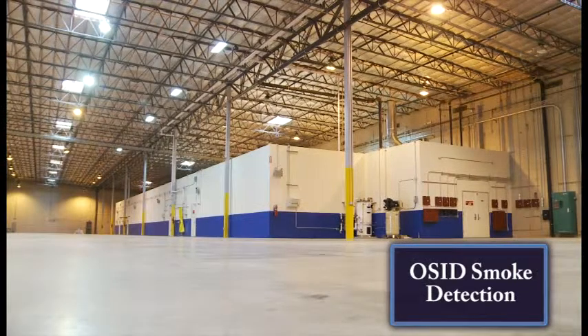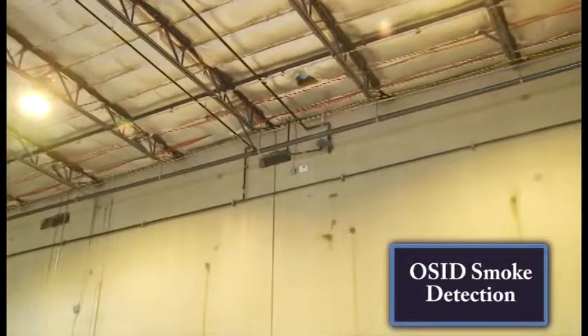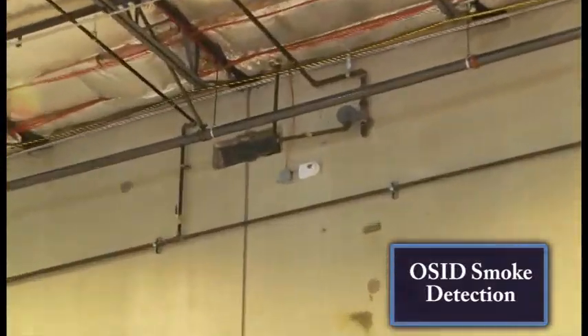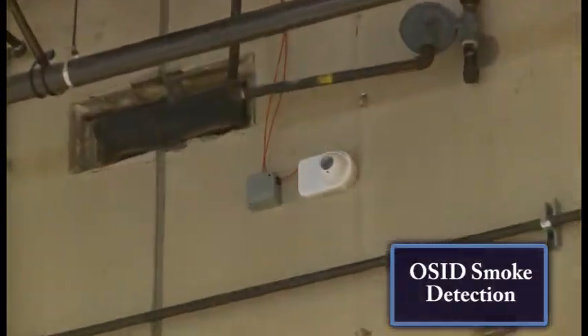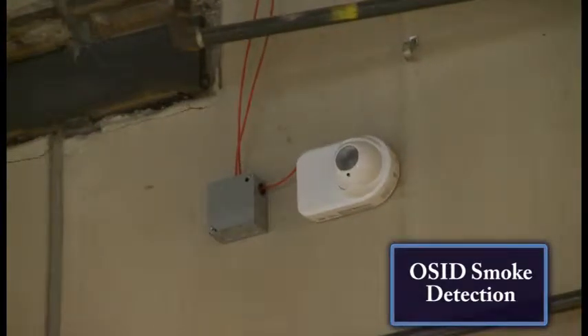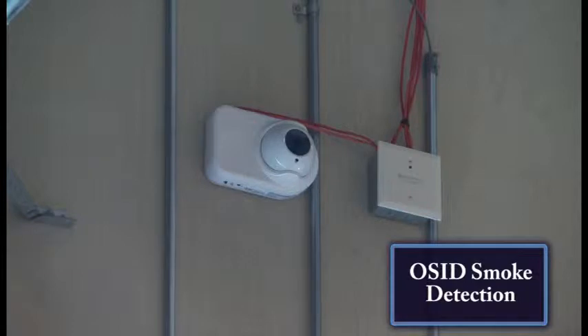The OSID smoke detector provides early warning of fire by measuring the amount of smoke entering invisible beams of light projected over the main warehouse area near the roof deck. New smoke detection technologies provide superior immunity to false alarms caused by dust and solid objects that may interfere with the beams. Innovations in optical imaging and signal processing enable the imager unit to locate the emitter unit without the need for precise alignment and compensate for natural building shifts.